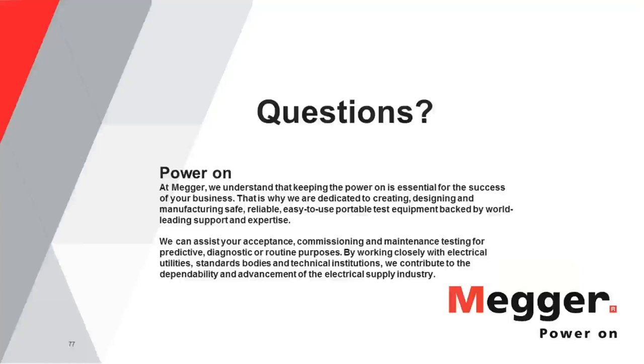Okay, thank you, Volney. Next question for Volney again. What does the SOP acronym mean? Well, I guess it's step of potential, one of the tests that Jeff mentioned, which is also a useful test to determine if an insulation is in good condition. This is a test in which you increase the voltage every minute over 5 steps, and you expect to get not a linear, but a constant value of resistance. Resistance should not change with the voltage you're applying. It should be a constant result.